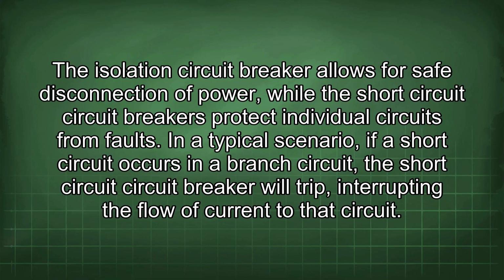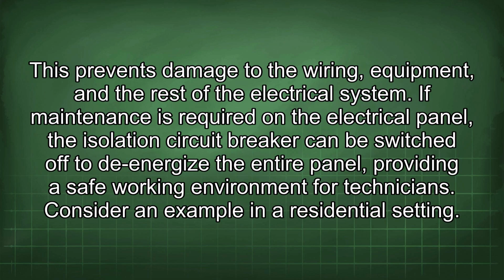In a typical scenario, if a short circuit occurs in a branch circuit, the short-circuit circuit breaker will trip, interrupting the flow of current to that circuit. This prevents damage to the wiring, equipment, and the rest of the electrical system. If maintenance is required on the electrical panel, the isolation circuit breaker can be switched off to de-energize the entire panel, providing a safe working environment for technicians.